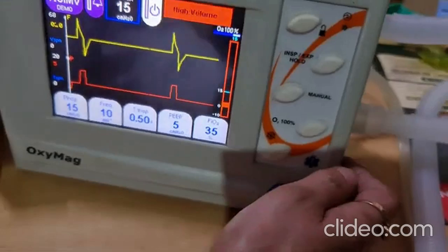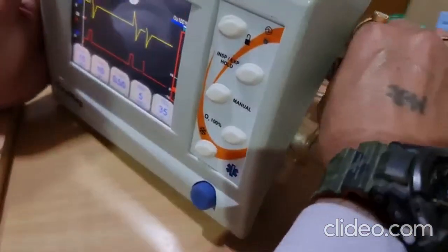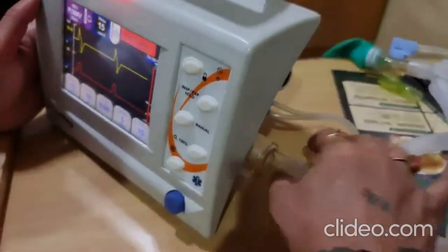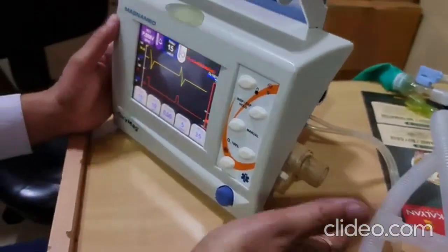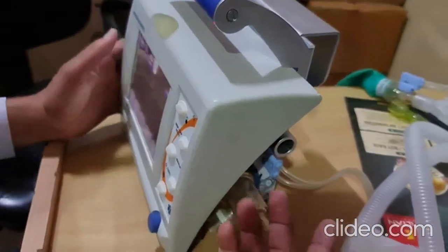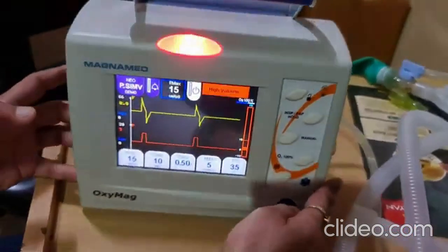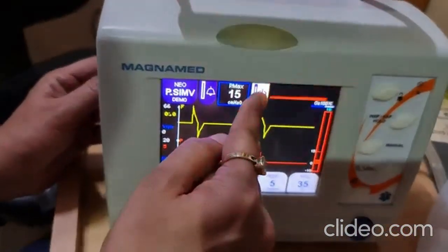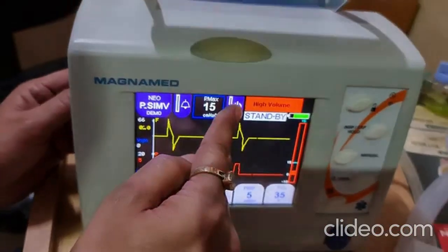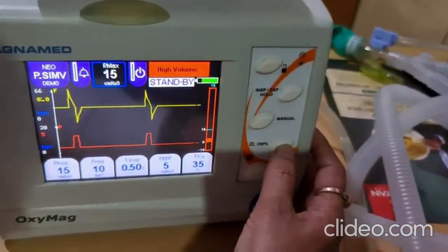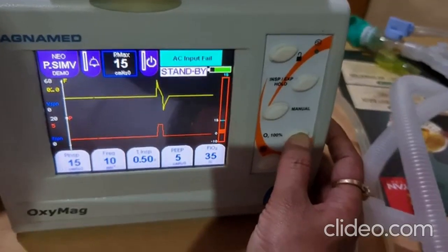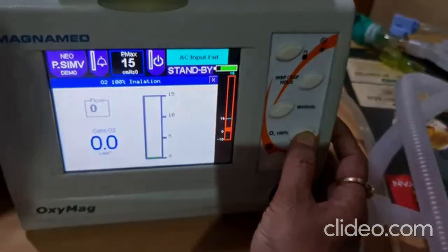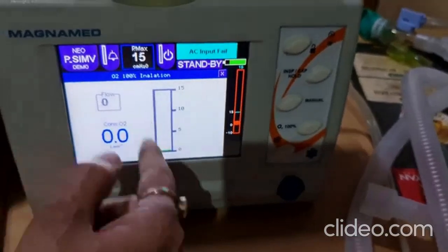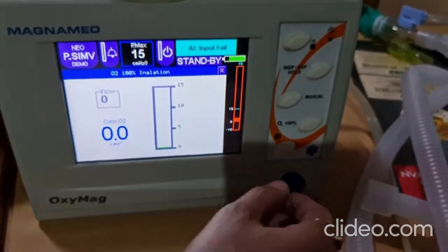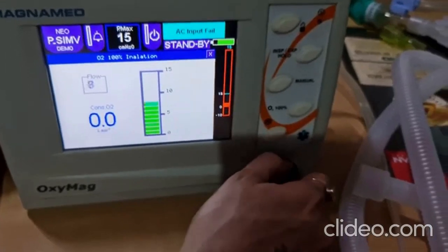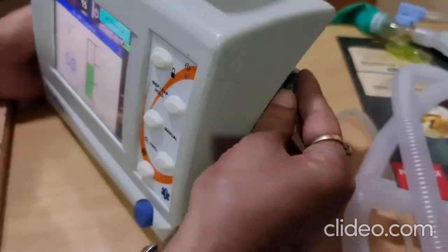And one more option is there. If you are using it in an ambulance and you want to use only oxygen, you want to connect a venti mask, you can bring it to standby. Now press this for 3 seconds. The electronic flow meter will come. Now you can increase or decrease flow. You will get oxygen supply here.